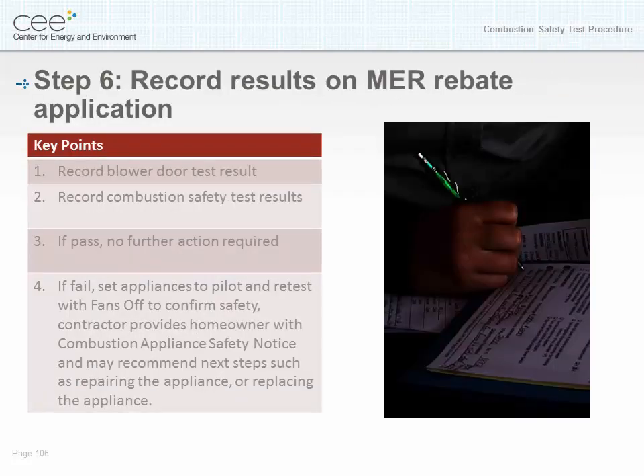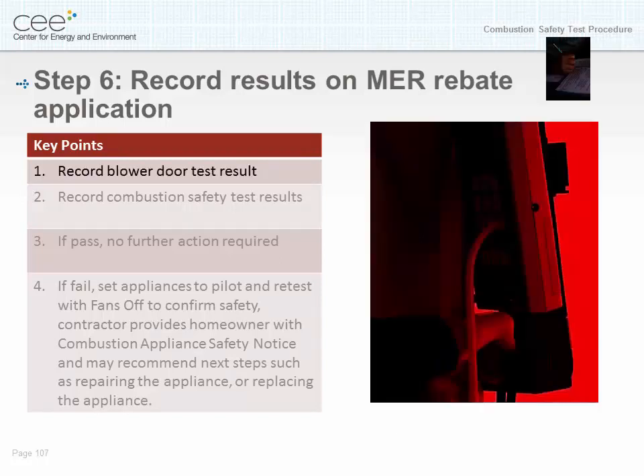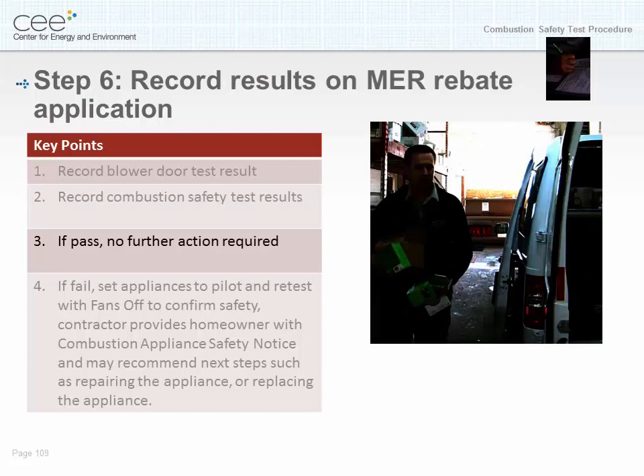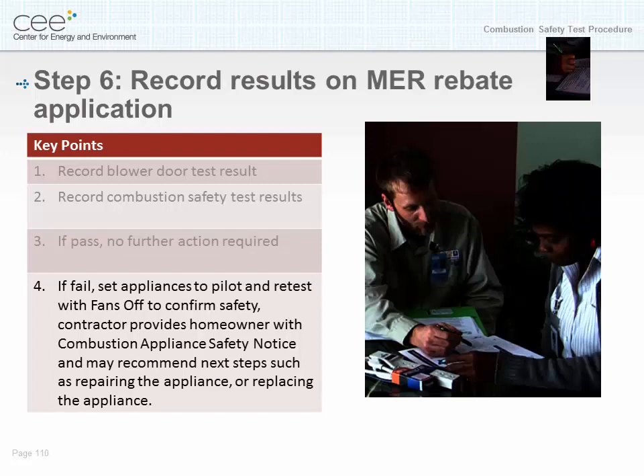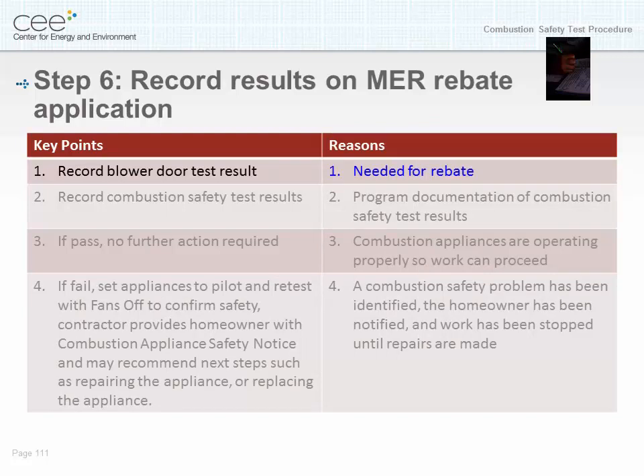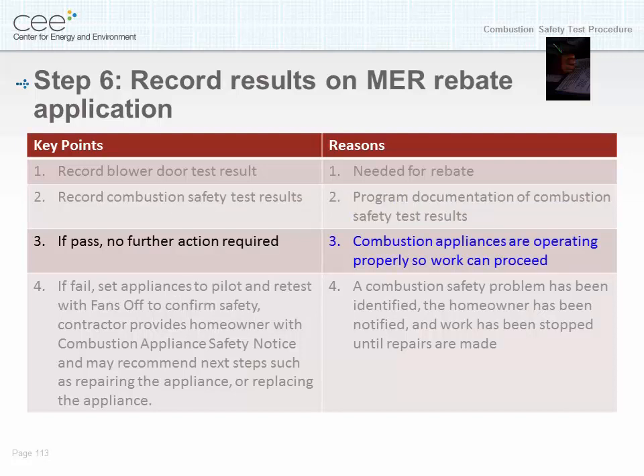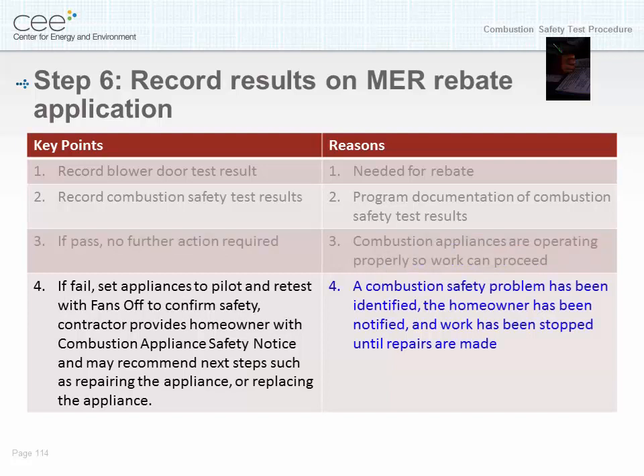Step six: record results on MER rebate application. Key points: record blower door test results; record combustion safety test results. If passed, no further action is required. If fail, set appliance to pilot and retest with fans off to confirm safety; the contractor provides the homeowner with a combustion appliance safety notice and may recommend next steps such as repairing or replacing the appliance. The blower door results are needed for the rebate. Program documentation records whether combustion appliances are operating properly or whether a combustion safety problem has been identified, the homeowner notified, and work stopped until repairs are made.